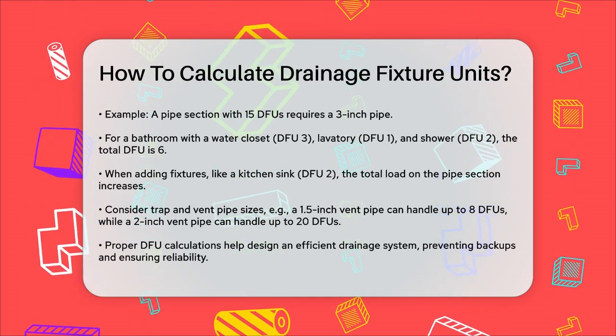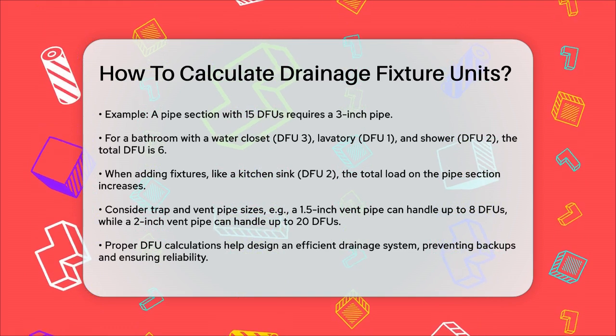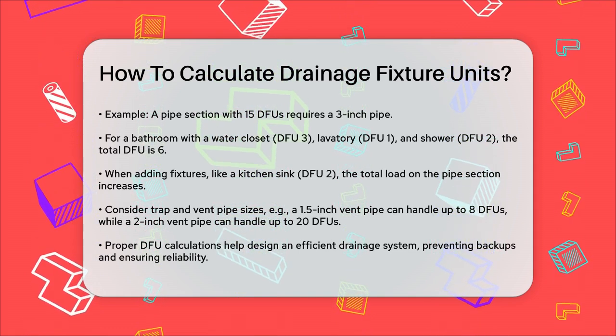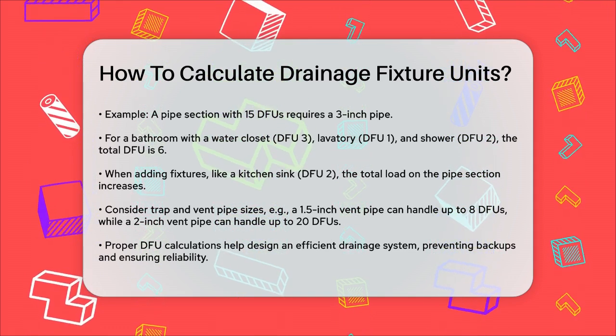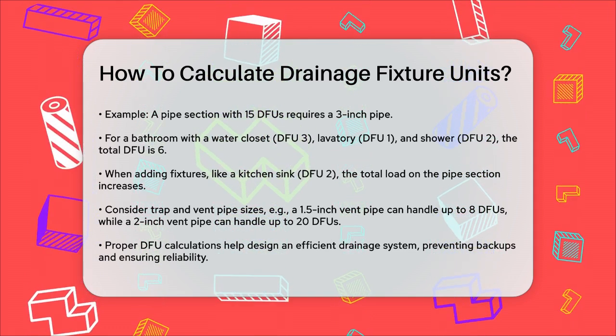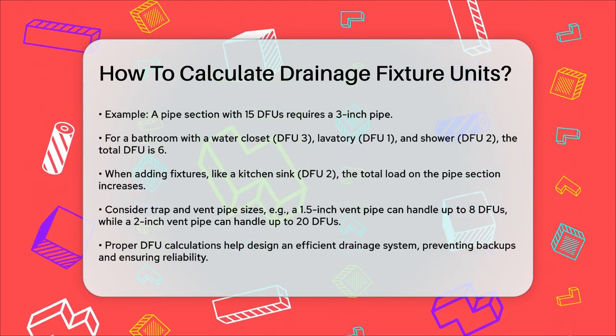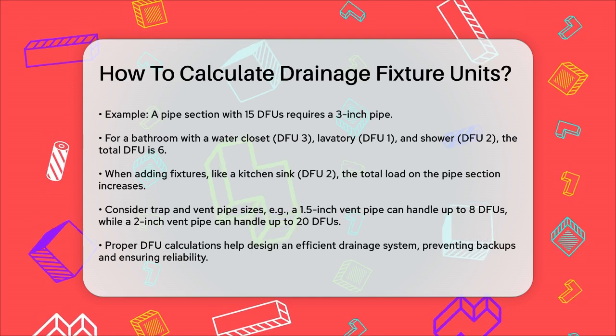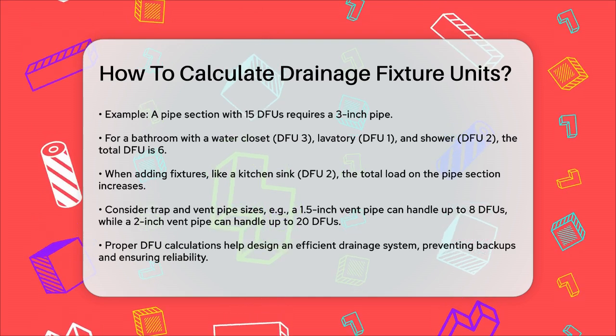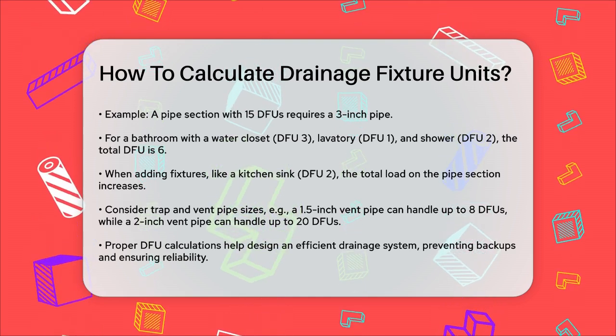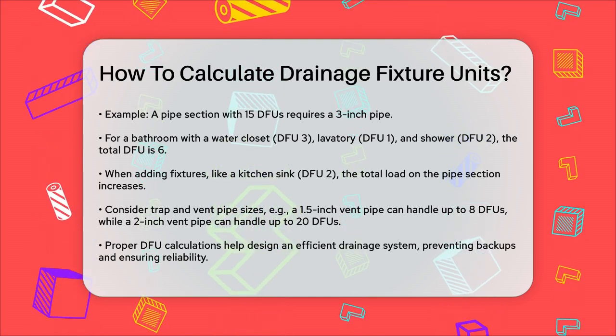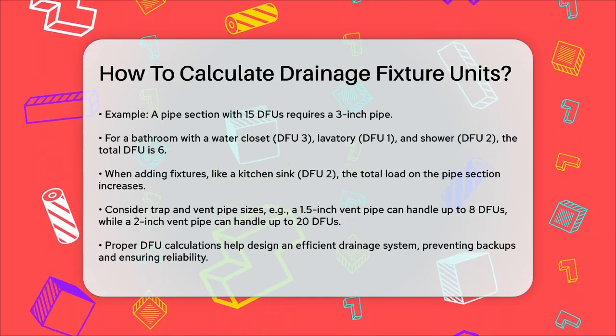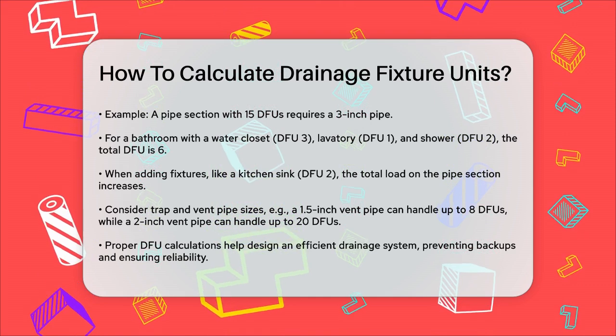Additionally, you need to consider the size of the traps and vent pipes. For instance, a 1.5-inch vent pipe can connect up to eight DFUs, while a two-inch vent pipe can handle up to 20 DFUs.